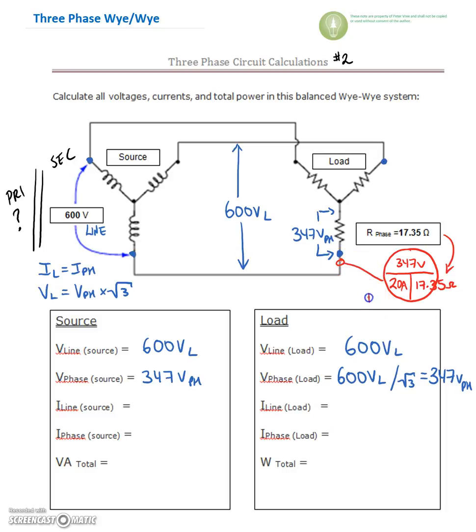Beautiful. That's the current that's flowing right there. So that's our phase current. We found that again by taking our 347 volts, dividing it by 17.35 ohms, and that gave us a phase current of 20 amps.